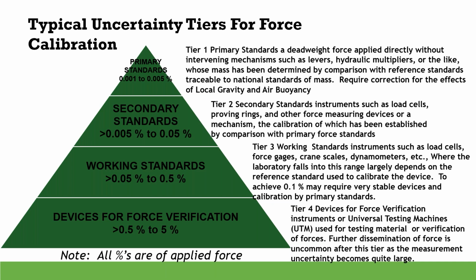And that can fall all over the place, but typically 0.05 to 0.5%. So this is much larger than the first tier, right? And then it keeps getting larger and larger. Devices for force verification are going to be greater than 0.5% to 5%, and that's usually a testing machine. Further dissemination of force is uncommon after this tier then certainly becomes quite large.